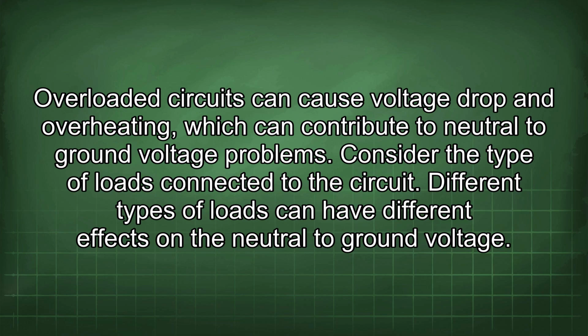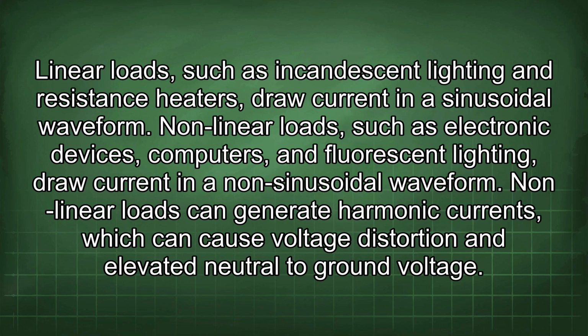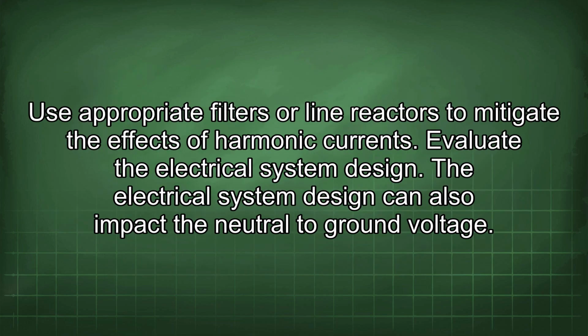Consider the type of loads connected to the circuit. Different types of loads can have different effects on the neutral to ground voltage. Linear loads, such as incandescent lighting and resistance heaters, draw current in a sinusoidal waveform. Non-linear loads, such as electronic devices, computers, and fluorescent lighting, draw current in a non-sinusoidal waveform. Non-linear loads can generate harmonic currents, which can cause voltage distortion and elevated neutral to ground voltage. Use appropriate filters or line reactors to mitigate the effects of harmonic currents.